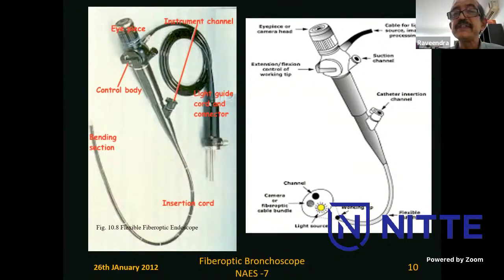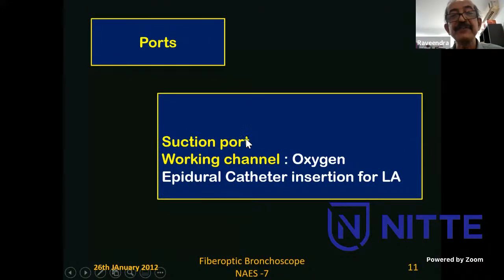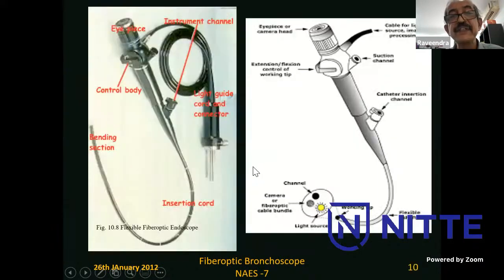Next you have various ports: the suction port and the working channel or channels. There's a suction channel with a control suction button that has a one-way valve; you connect the suction to the suction port. Through the working channel you can pass instruments. This one has only one working channel, with a proximal opening in the control or handle, and a distal opening at the tip. Then you have a control lever, which we'll discuss more as we move on.